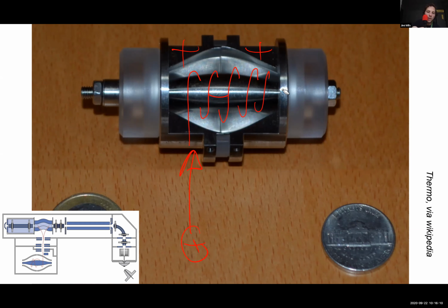Then what happens is, for a particular ion, it will form a band of ions of that particular mass-to-charge ratio. For a particular mass-to-charge ratio, a discrete band will form, and then that band oscillates up and down the axis of this device. The rate that it oscillates is proportional to charge over mass. And so from the frequency that you get from this thing going up and down, you can figure out what the mass-to-charge ratio is.